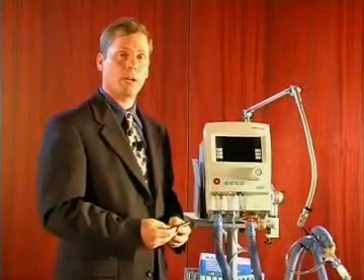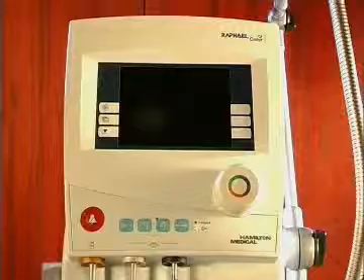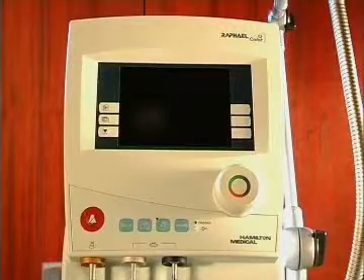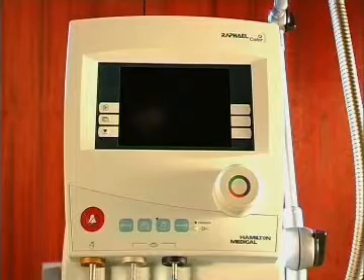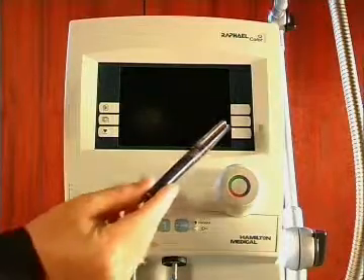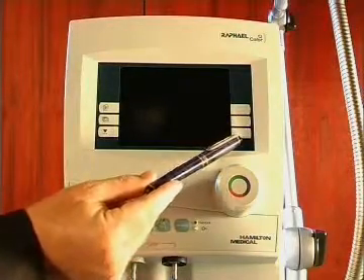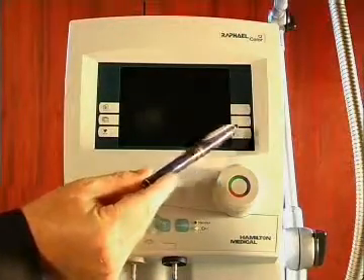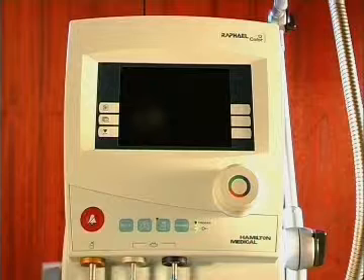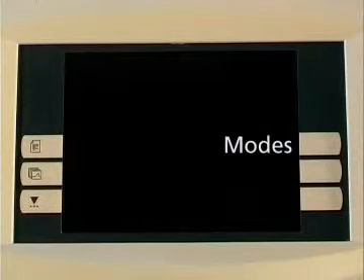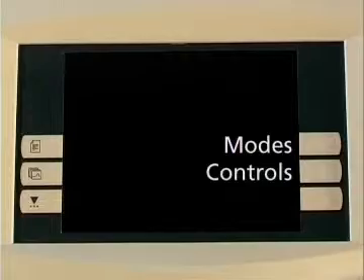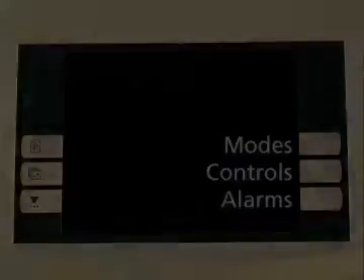In addition to the push and turn knob, we have hard keys in different places on the ventilator. We have hard keys on the right-hand side that will open windows from that screen. On the right-hand side, this will access modes, controls, and alarms.